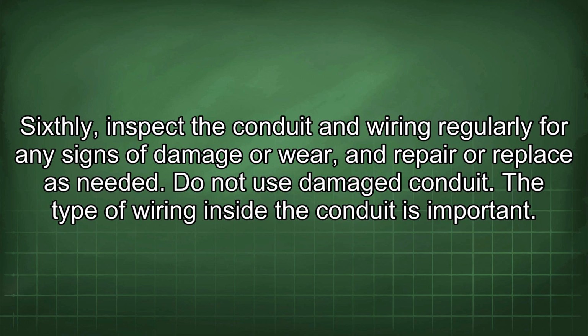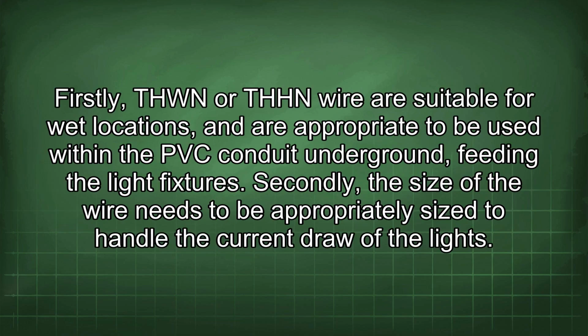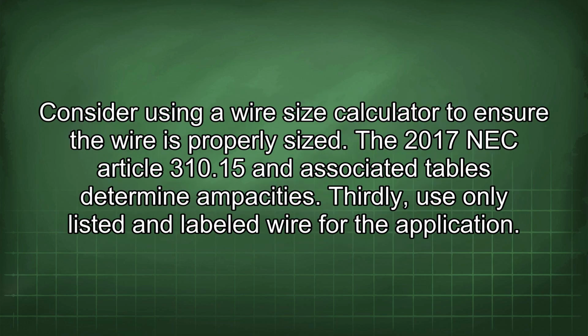The type of wiring inside the conduit is important. Firstly, THWN or THHN wire are suitable for wet locations and are appropriate to be used within the PVC conduit underground, feeding the light fixtures. Secondly, the size of the wire needs to be appropriately sized to handle the current draw of the lights. Consider using a wire size calculator to ensure the wire is properly sized. The 2017 NEC Article 310.15 and associated tables determine ampacities.